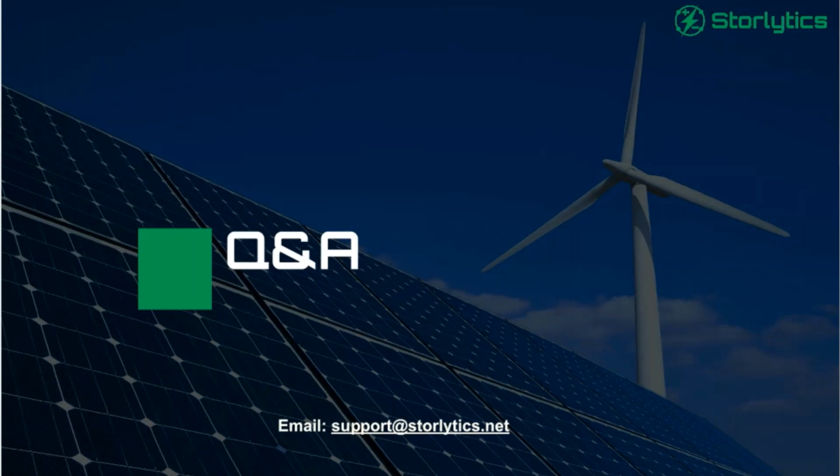Yeah. So one of the characteristics of lithium is that if you have a very high depth of discharge, going from 0 to 100%, that kind of cycle has a much more detrimental effect on degradation. You also have to look at your average resting state of charge. Typically, the higher it is, the more impactful it is on degradation. So our platform takes those into account.